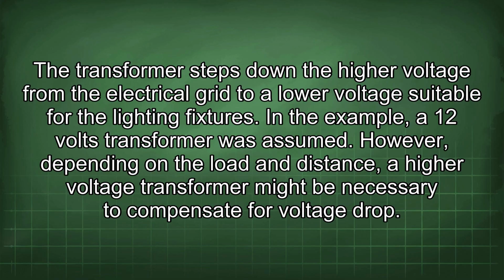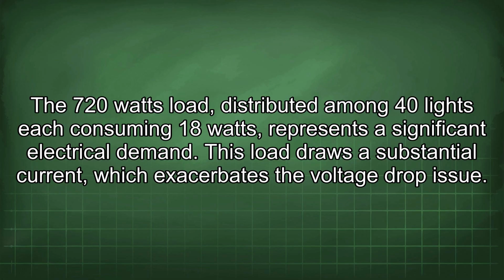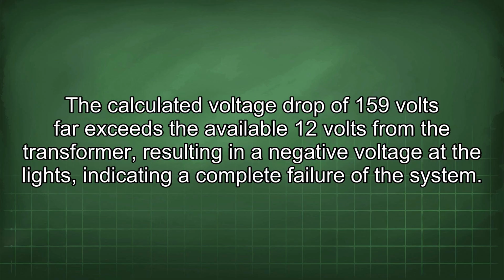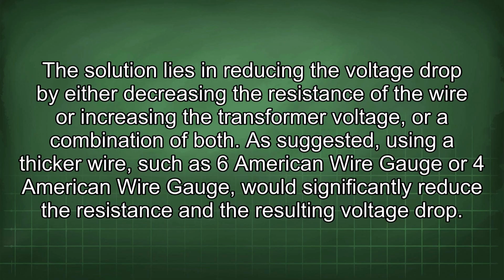However, depending on the load and distance, a higher voltage transformer might be necessary to compensate for voltage drop. The 720 watt load, distributed among 40 lights each consuming 18 watts, represents a significant electrical demand. This load draws a substantial current, which exacerbates the voltage drop issue. The calculated voltage drop of 159 volts far exceeds the available 12 volts from the transformer, resulting in a negative voltage at the lights, indicating a complete failure of the system. The solution lies in reducing the voltage drop by either decreasing the resistance of the wire or increasing the transformer voltage, or a combination of both.